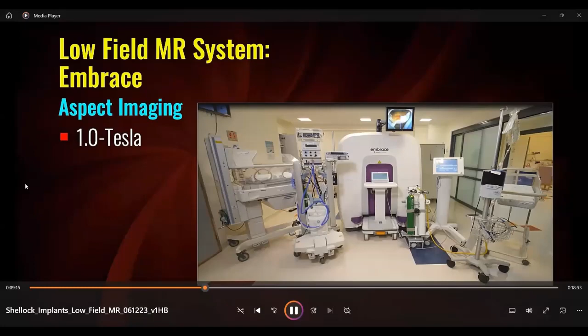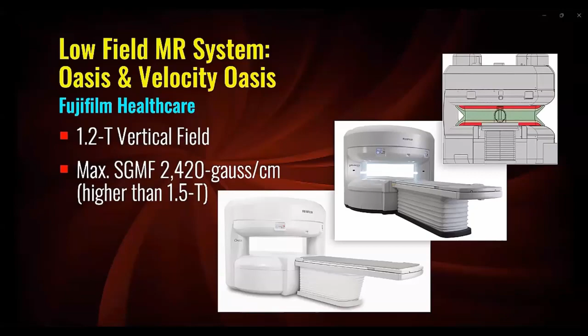Finally, there are MR systems that operate just under 1.5 Tesla, namely the Oasis and the Oasis Velocity vertical field 1.2 Tesla scanners from Fujifilm Healthcare. These systems have a maximum spatial gradient magnetic field of 2,420 Gauss per centimeter, which is higher than the maximum spatial gradient magnetic field values that are associated with 1.5 Tesla horizontal field scanners. The possible implications of this 2,420 Gauss per centimeter spatial gradient magnetic field with respect to the force acting on a passive implant is discussed later in my presentation.